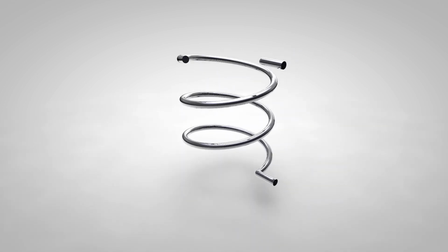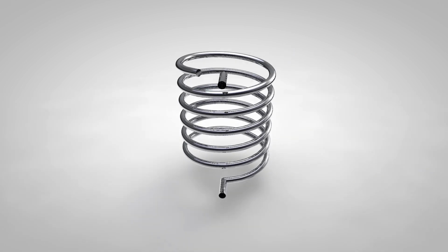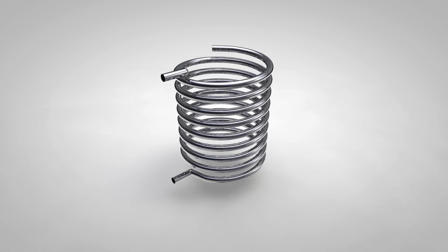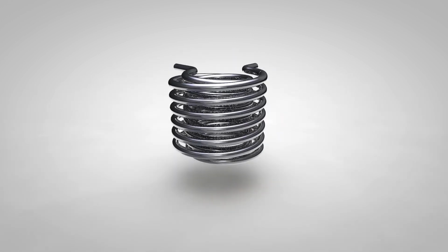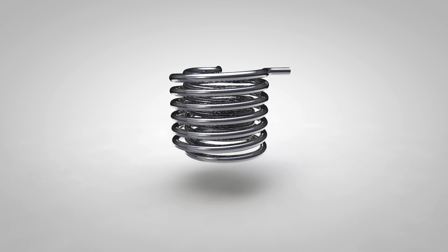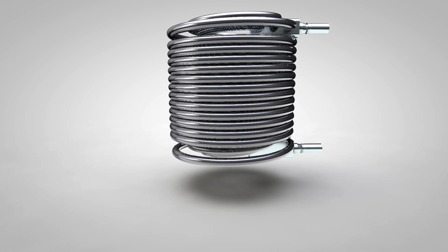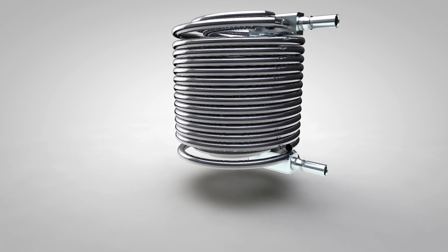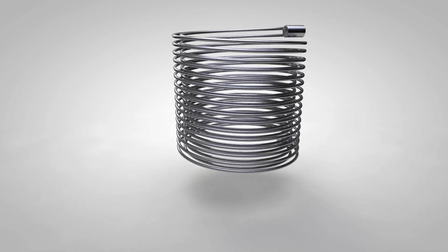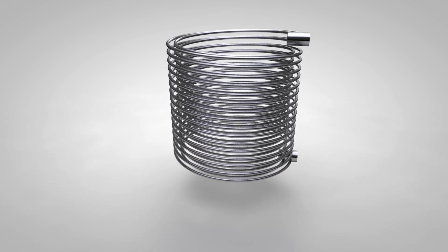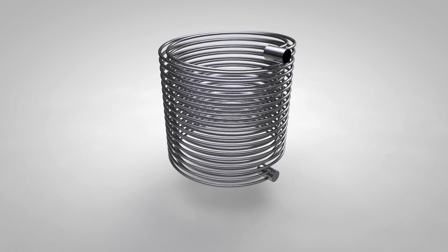The kilowatt rating of the coil can be changed by increasing or decreasing its surface area. The more surface area, the greater the heat transfer is, the higher the kilowatt rating. Bear in mind, the kilowatt rating is only an indication of the maximum potential output. It needs energy from the heating system in the form of the right water temperature, flow rates, and pipe sizes in order to achieve it.